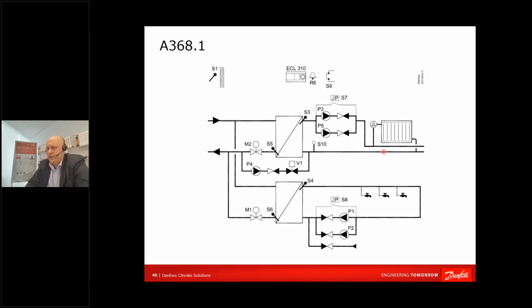Both scenarios, as a stick has two ends, can be used. You can use a smart pump if you have a possibility to get an external alarm contact. You might connect it to S9, then ECL will discover that there is something wrong in the station.